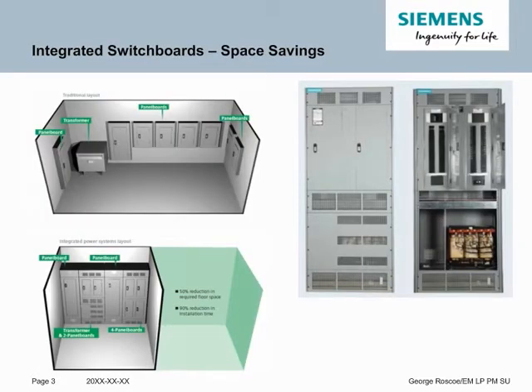An example of how an IPS switchboard can save space is the floor space taken up by traditional panel boards and transformers. In this example, you have 7 panel boards and 1 transformer lying about the electrical room. By combining them into an integrated power system switchboard, you can stack the lighting panels on top of each other and also put the transformer underneath the lighting panel. This saves 50% of floor space, and by having these integrated together and not wiring individually, you save up to 90% on installation time.